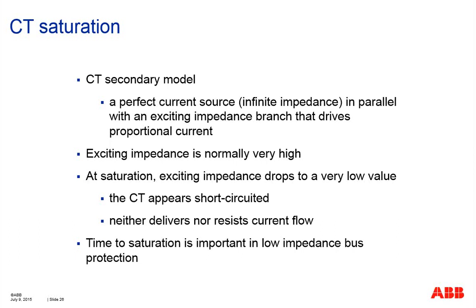This kind of situation is very important in any low impedance bus protection. Modern bus protection only requires maybe down to 2 to 3 milliseconds of healthy replica of the primary current for the bus protection to operate properly, even in external heavy CT saturation conditions.